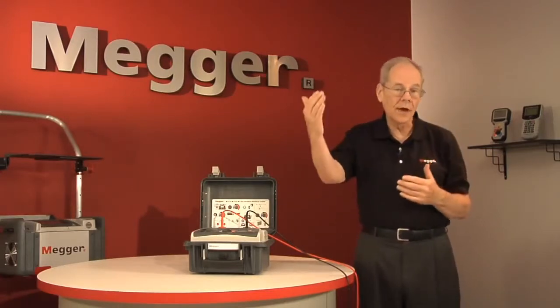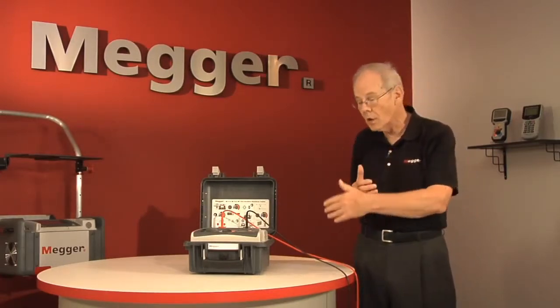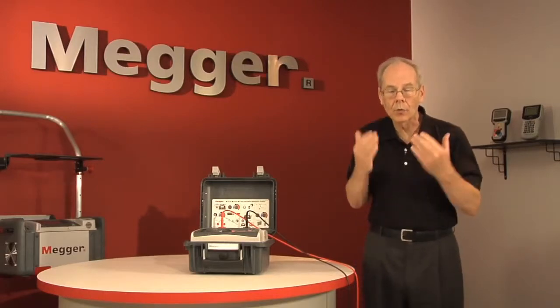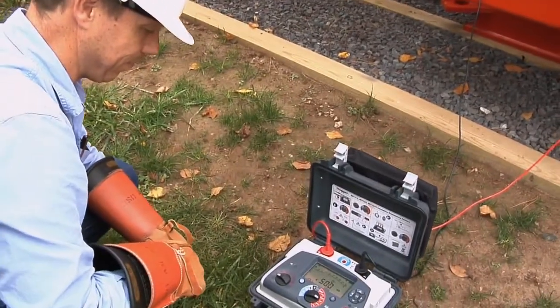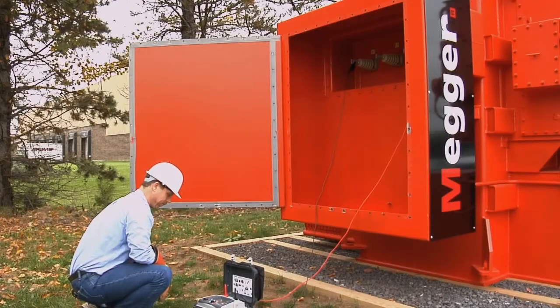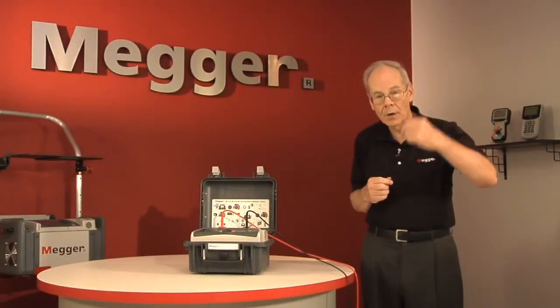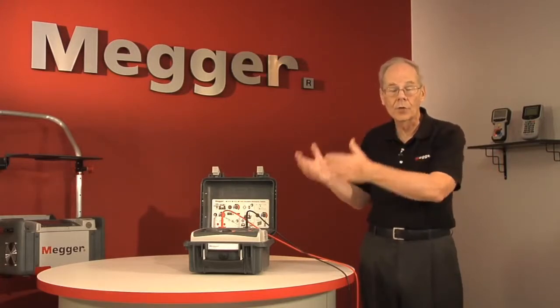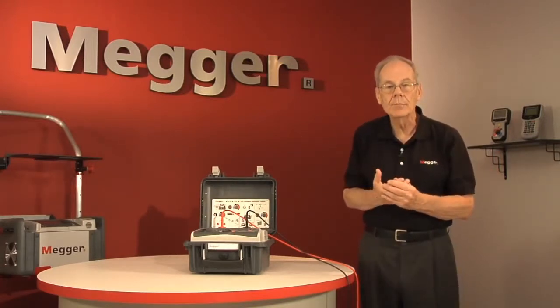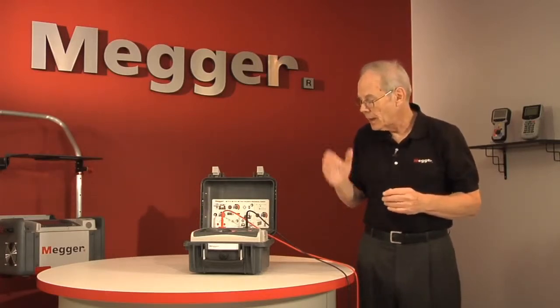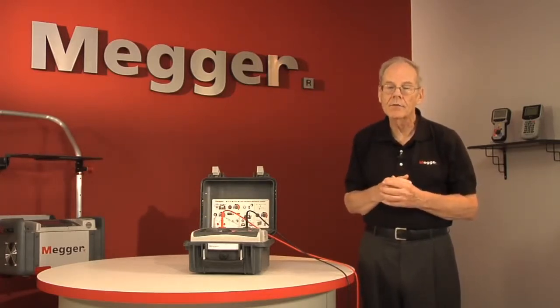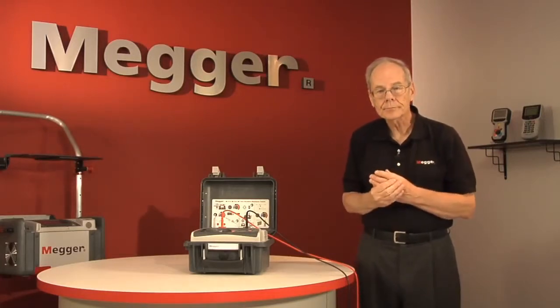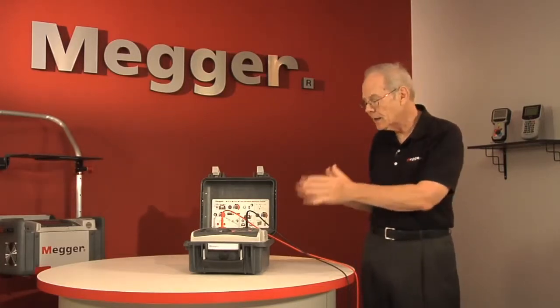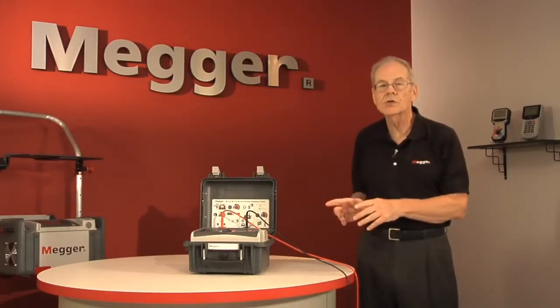So if you selected a 10 kV ceiling, for instance, then it will start with a 2 kV test. It will run that for 1 minute. The operator can stand and watch all the information up on the display and watch the progress of the test. The time, of course, is shown, and when you come to 1 minute, the test will automatically ramp up the voltage now to 4 kV and run that for the second minute, and so on in 5 increments up to your ceiling of 10 kV. At that time, the test will terminate automatically, and again, all the critical information remains on the display.